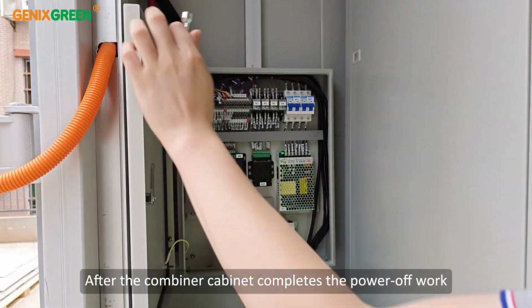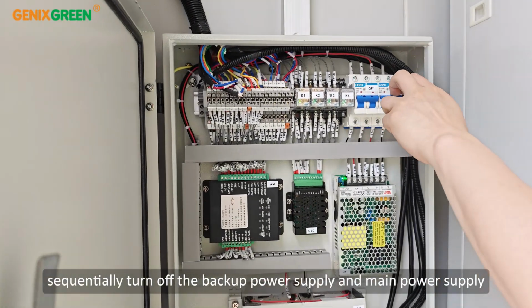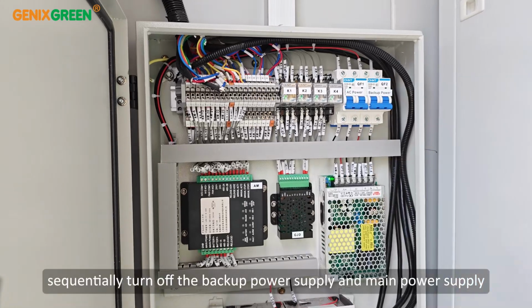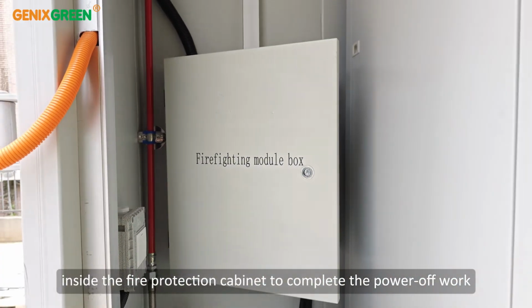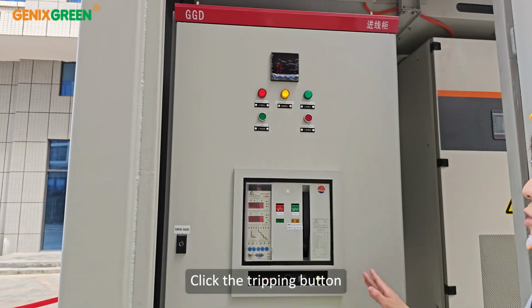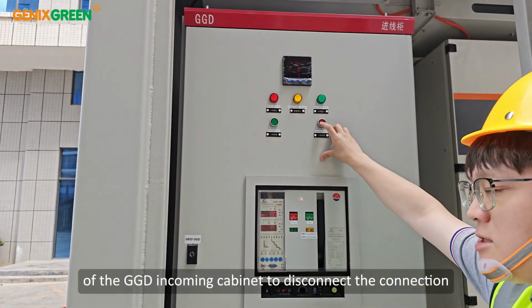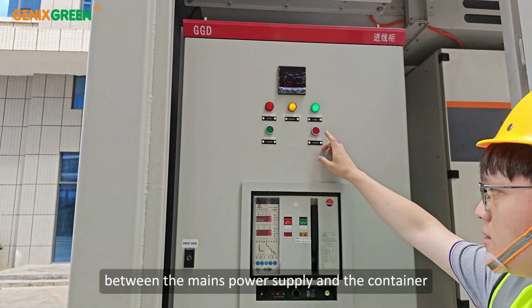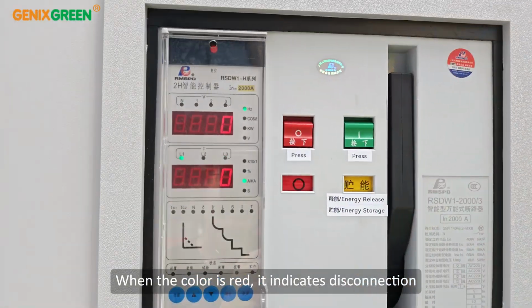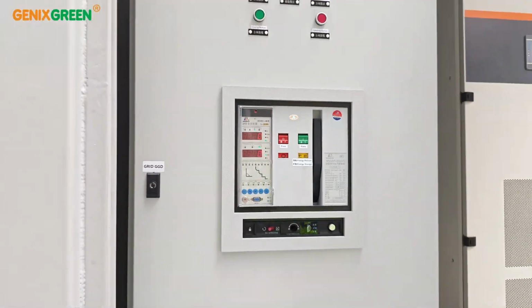After the combiner cabinet completes the power off work, sequentially turn off the backup power supply and main power supply inside the fire protection cabinet to complete the power off work. Click the tripping button of the GGD incoming cabinet to disconnect the connection between the mains power supply and the container. When the color is red, it indicates disconnection.